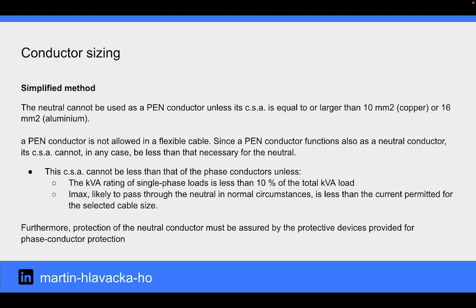The neutral cannot be used as a PEN conductor unless its CSA is equal to or greater than 10 mm squared for a copper conductor or 16 mm squared for an aluminum conductor. Moreover, a PEN conductor is not allowed in a flexible cable. Since the PEN conductor functions also as a neutral conductor, its CSA cannot in any case be less than that necessary for the neutral. Furthermore, the protection of the neutral conductor must be assured by the protective devices provided for phase conductor protection.